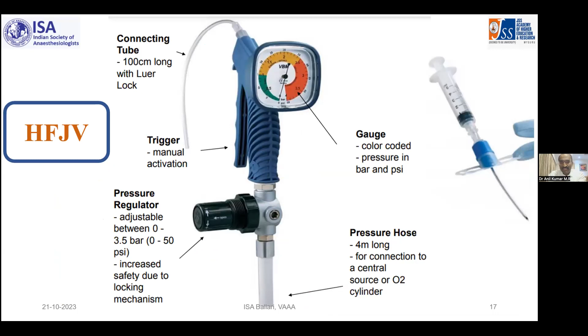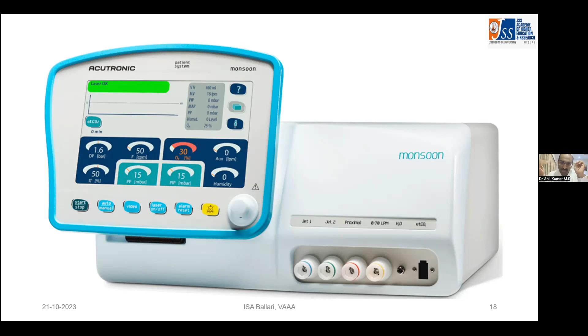The other equipment, available extensively in the US but not yet available in India, is a machine called the Monsoon from the company Acutronic. If you see carefully, we can set the driving pressure somewhere between 1 to 5 bars. The frequency can be adjusted from 50 to 250. The FiO2 can be adjusted between 30 to 100%. And we can even set the limits of the pressure. That is a safety feature. Anytime the set pressure is exceeded, the jet ventilator automatically stops producing the jet ventilation, which prevents volutrauma or barotrauma to the patient. It also has a button. If you carefully see the fourth button, there is a laser button. During a laser procedure, the minute you press the laser button, the FiO2 falls from 1 to 0.3.